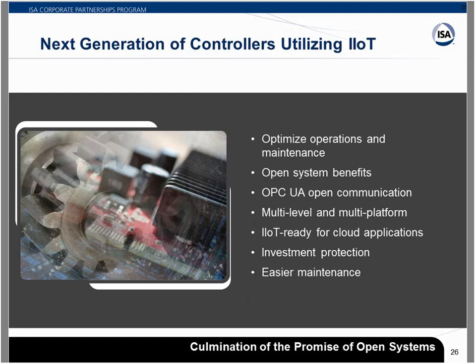In the past, there was a lot of OPC Classic, I'll call it, that was used, and that typically required the model that Graham was showing, where you'd have your controller, then you'd have something like an I/O server, and then you might have your SCADA DCS platform where it was normalized through the I/O server. So an OPC Classic type server, typically a piece of software running on a PC somewhere, translating the machine protocol - stuff like EtherNet/IP, Modbus, Profibus - into something that the SCADA system could interpret. Typically OPC was a common mode for that.